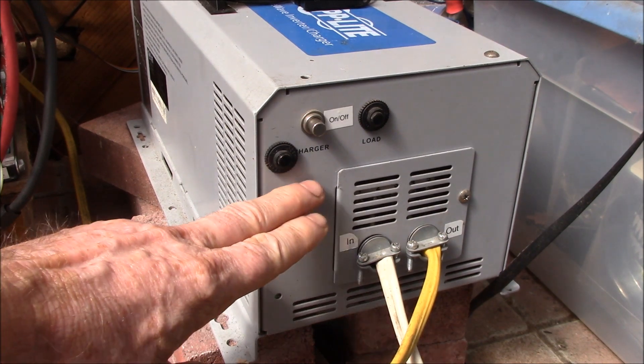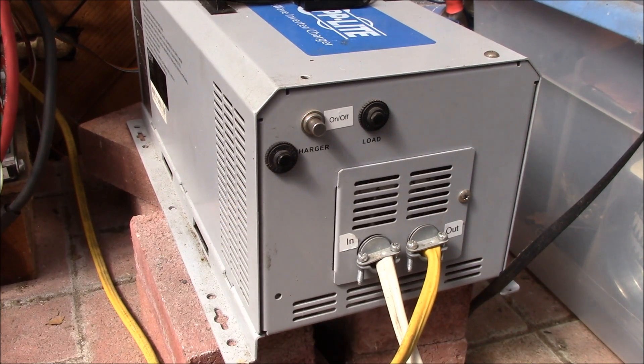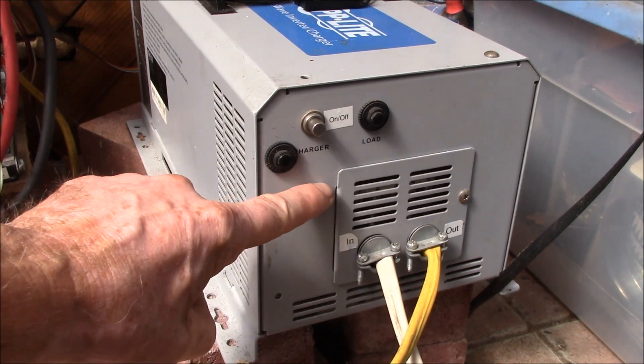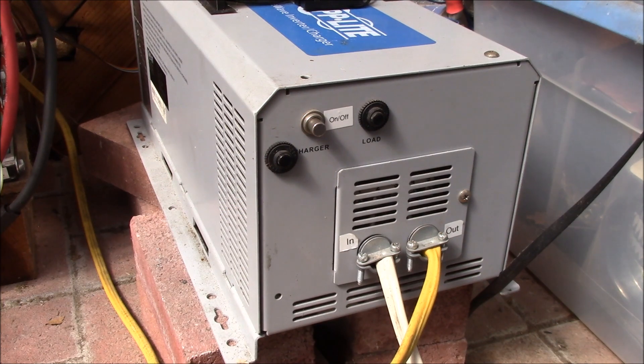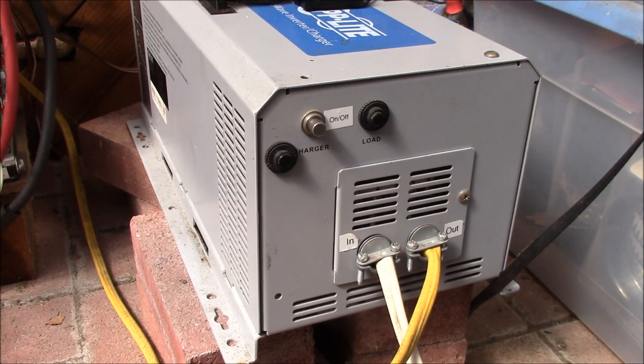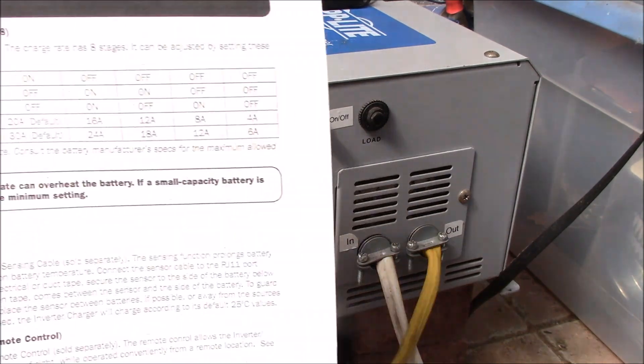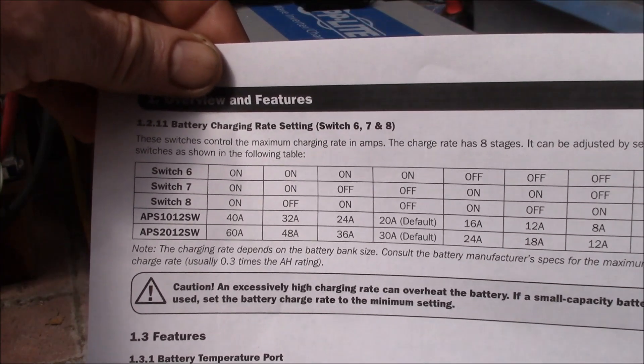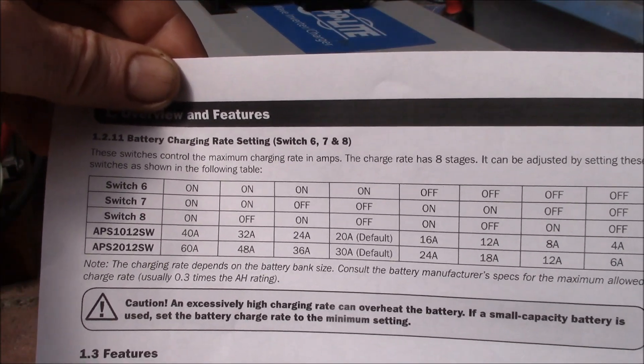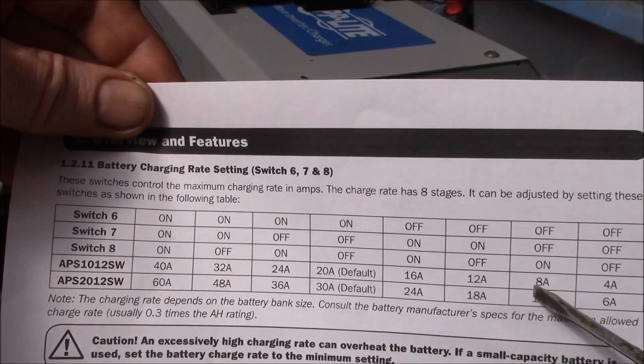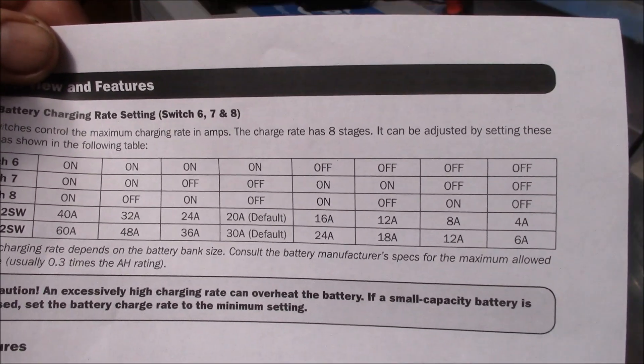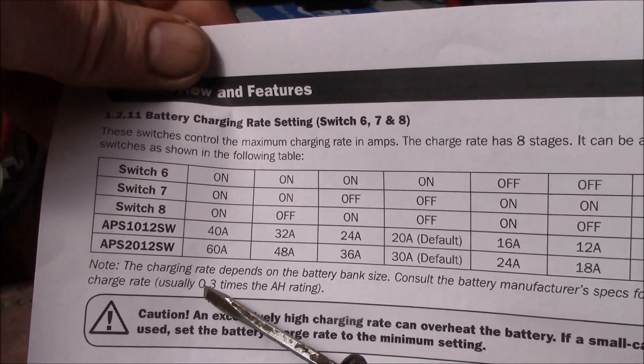When I first noticed that, I contacted Tripp Lite technical support and I asked them is there any way you can turn the charger in this thing off. They told me nope, you cannot turn it off. You can go down to four amps and that's the lower limit.